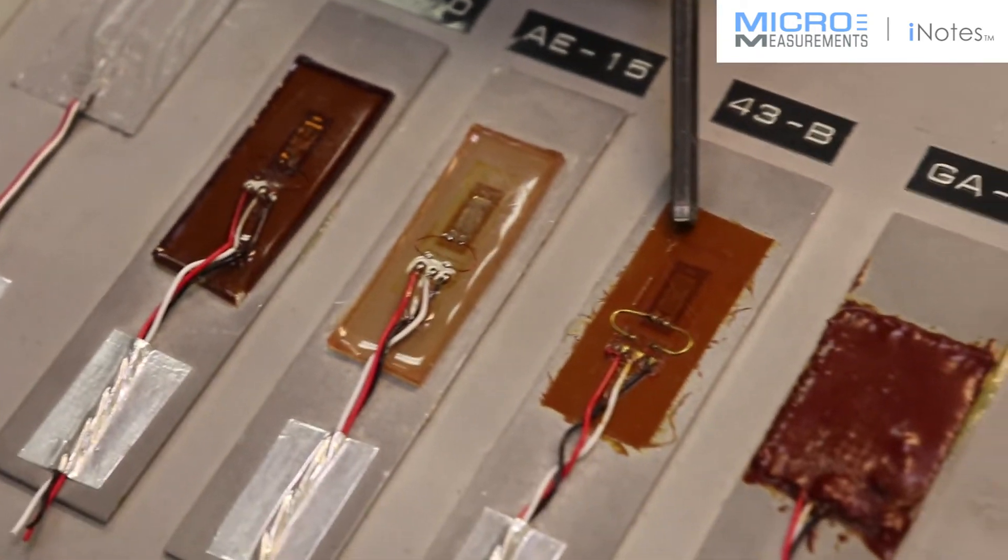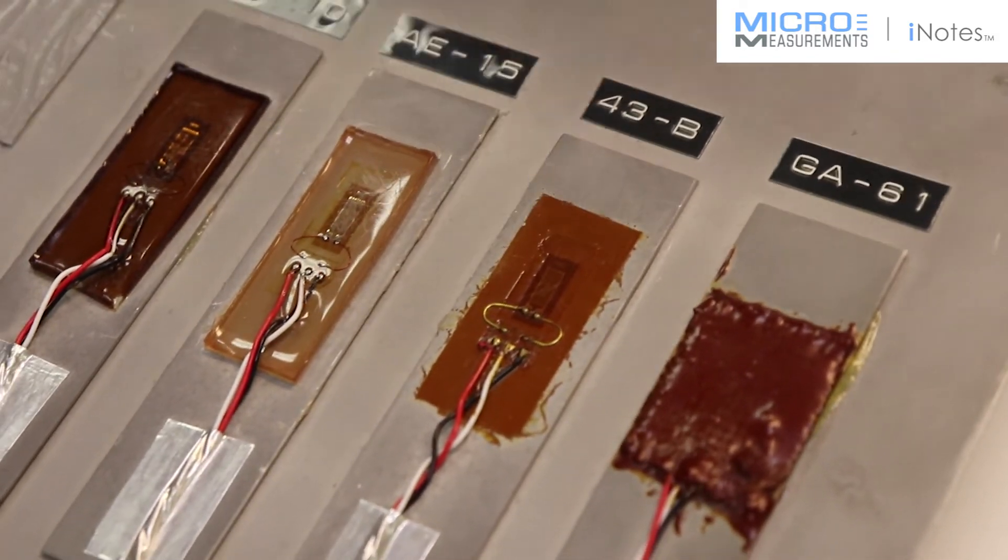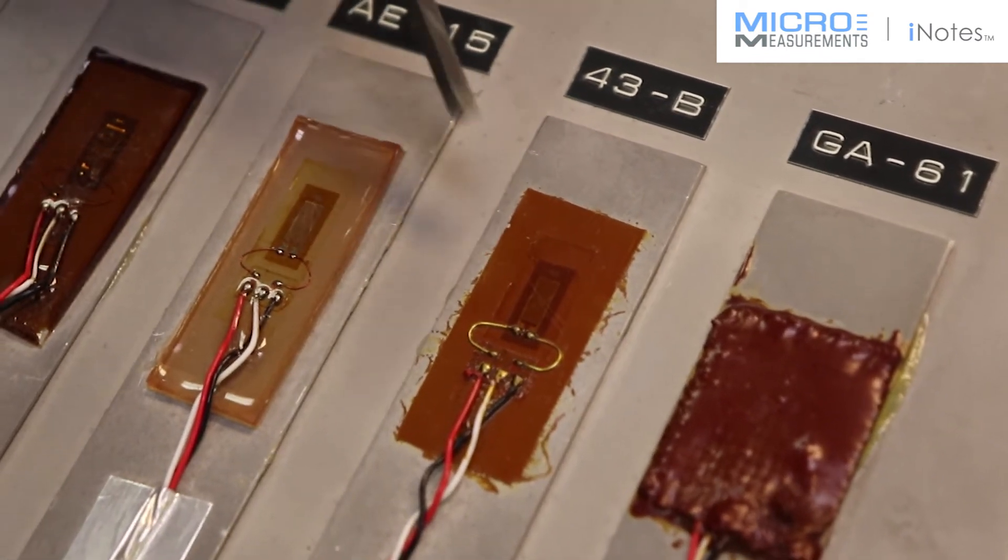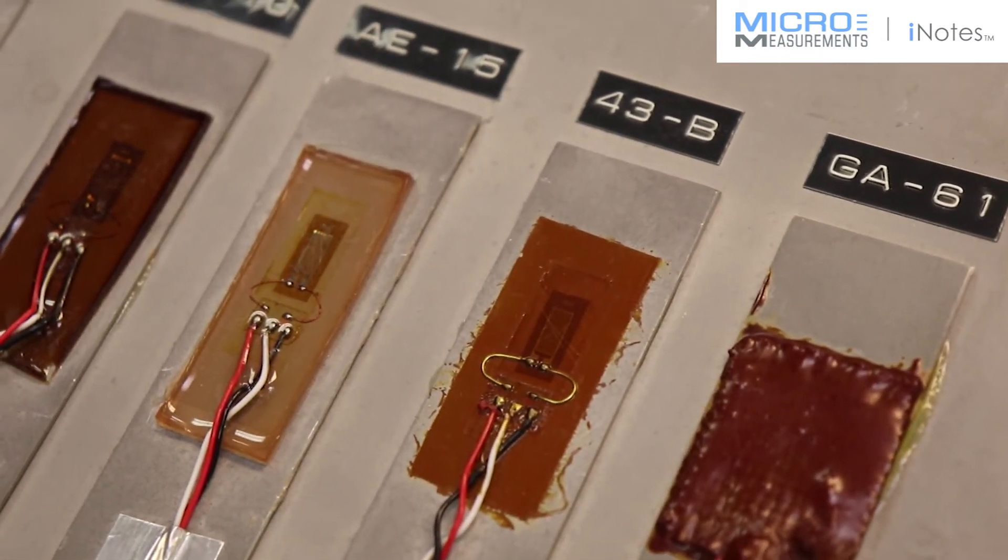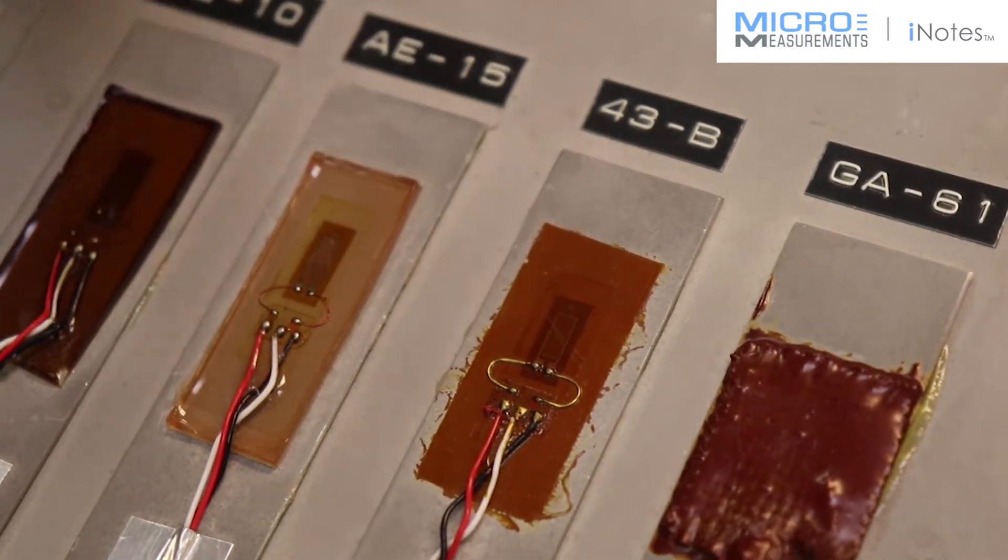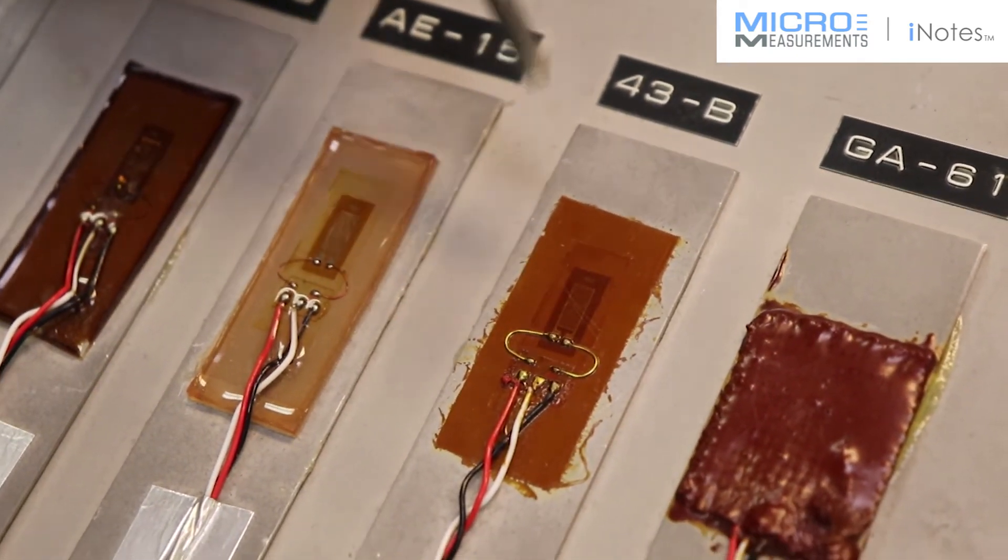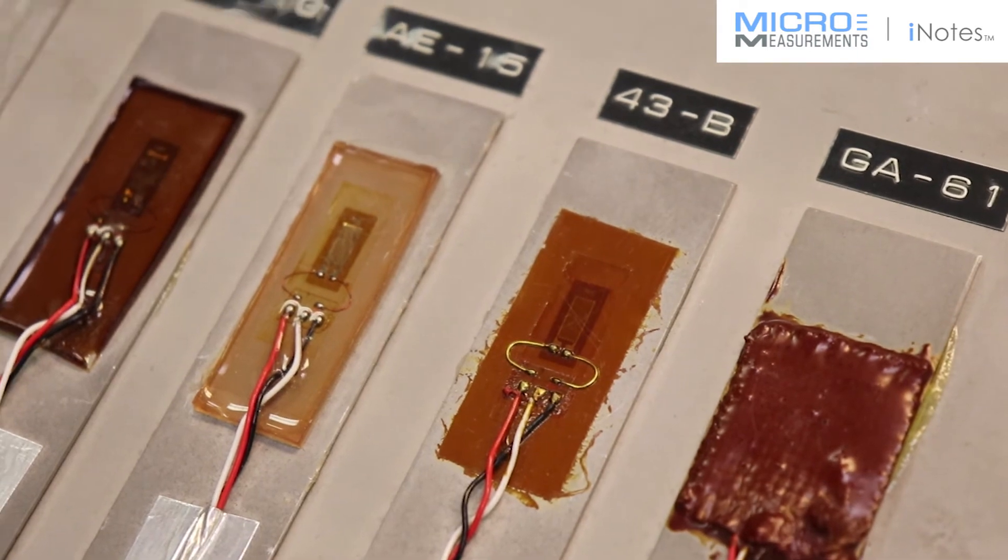The next one is 43B. This is an epoxy phenolic adhesive system that has a filler in it, a little bit of colloidal clay. And this is used typically in deep cryogenic applications. Where you have a deep cryogenic test, you want to have a fairly thin environmental protection that's not going to disrupt or crack when you go to those temperatures.